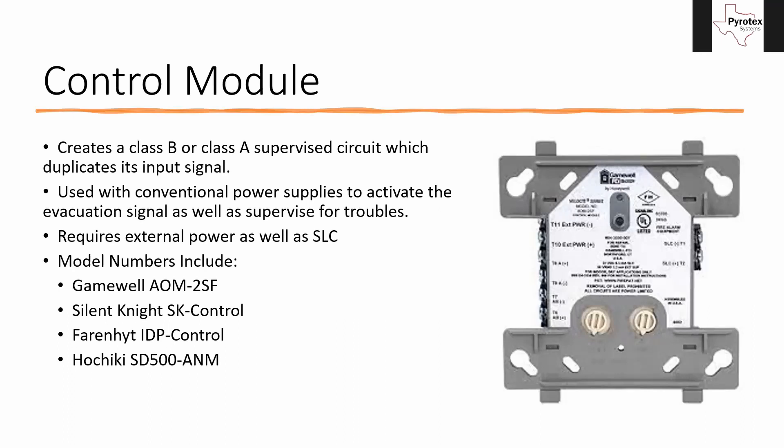This will require two different sources. One, you have to have that external power — whether it's a speaker circuit or auxiliary power. It also has to have SLC. The SLC is how it communicates to your fire alarm control panel. The external power is how it actually provides its control function. I also put a list of different model numbers for working on different product lines: Gamewell is AOM2SF, Silent Knight is SK-Control, Farenhyt is IDP Control, and Hochiki is SD500-ANM, short for addressable notification module.